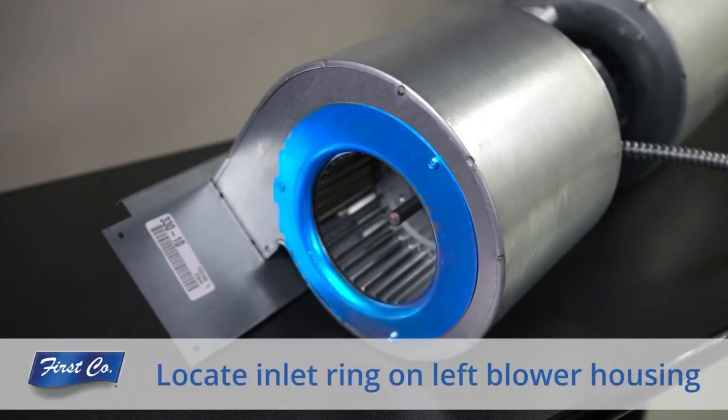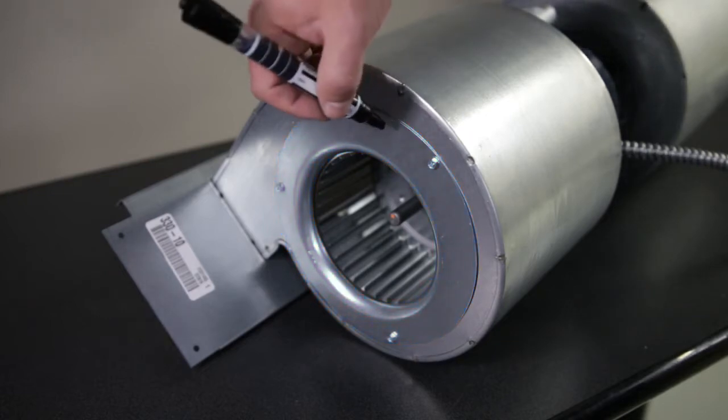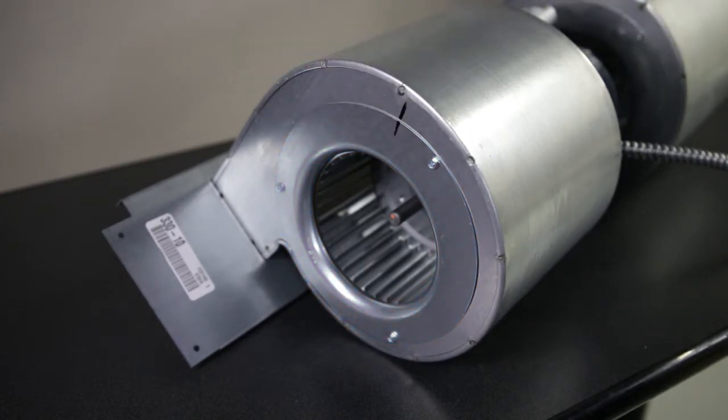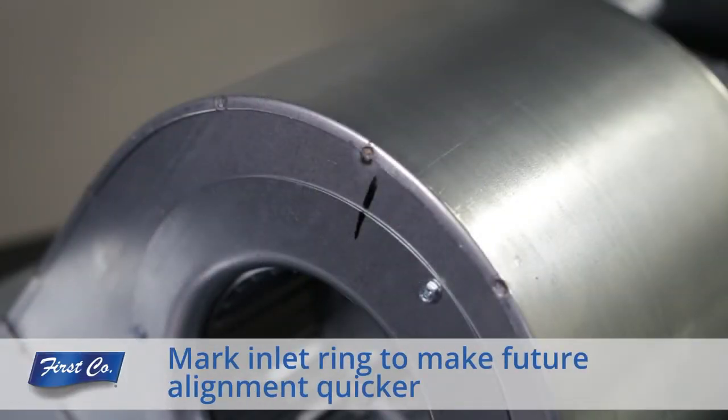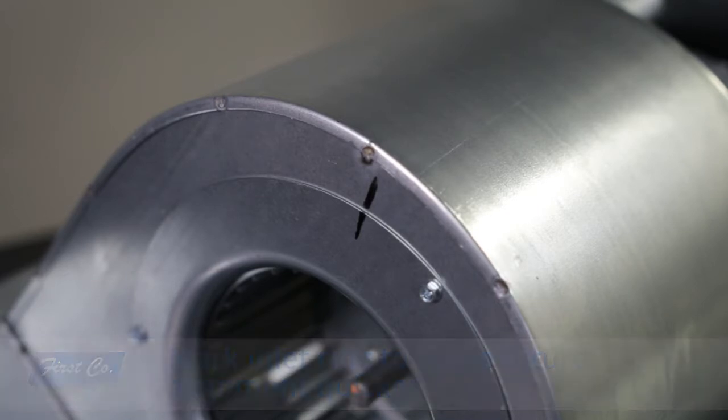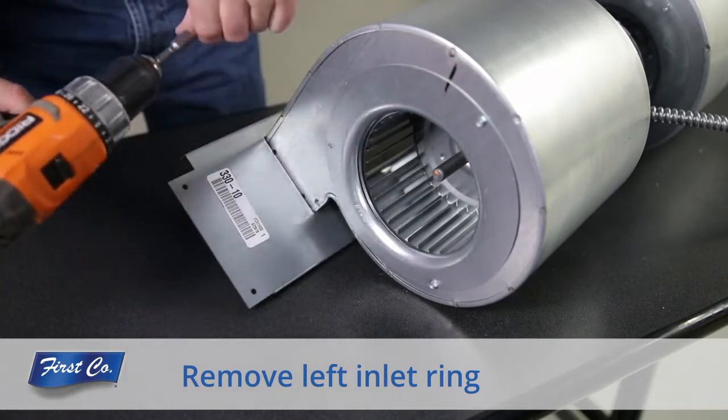First, locate the inlet ring on the left blower housing. In order to make reinstalling the fan motor easier, it is recommended that you mark the outside of the inlet ring with a pencil or marker to make the inlet ring realignment and reinstallation quicker. Remove the left inlet ring and set it to the side for reinstallation.